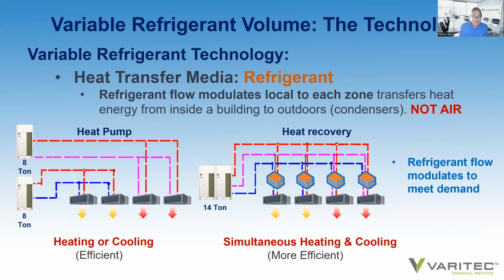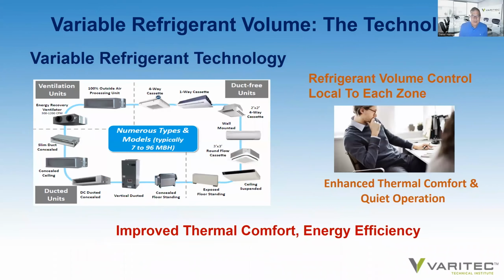And the types of air handlers that are utilized for these systems vary in types of product. They can be ducted indoor air handlers, so you can serve multiple rooms from a common VRV unit, or they can be cassettes in each zone, whether ceiling or wall mounted, so that we can actually strategically bring that refrigerant to each room where we have the greatest efficiency available to the greatest number of zones.